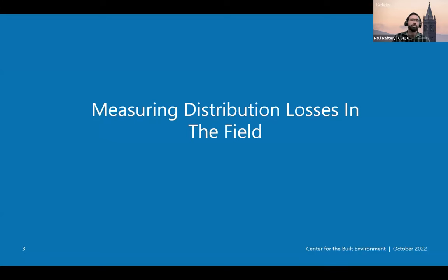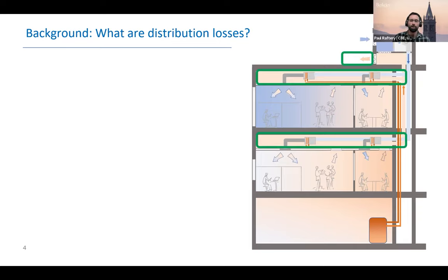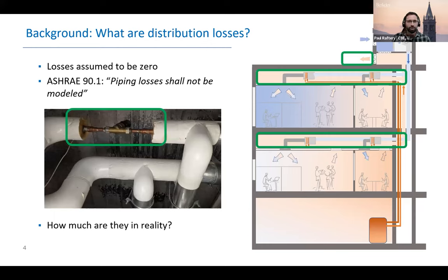One scope element is measuring distribution losses from heating hot water systems in the field, and then gathering lots of data from these systems and analyzing it to yield insights that we can use to save energy. So first, looking at these distribution losses — essentially the heat loss from hot water piping distributed throughout the building, basically the heat required to keep that piping warm and maintain hot water at all end uses, reheat coils, and baseboard devices. Generally in analysis, these losses are assumed to be zero. ASHRAE 90.1 actually requires that piping losses shall not be modeled. But even from first principles, we know they're not zero. And in practice, in real buildings, you have lots of sections of piping — even in new buildings, sections of completely uninsulated piping and valves.